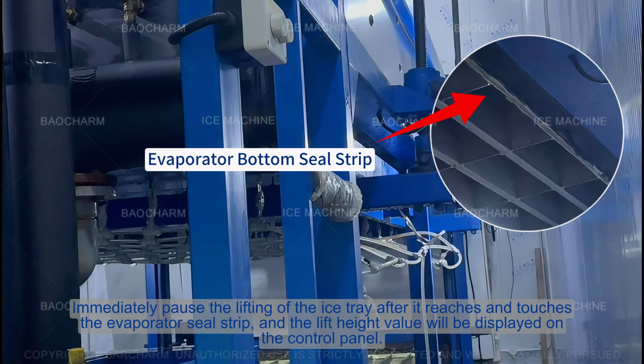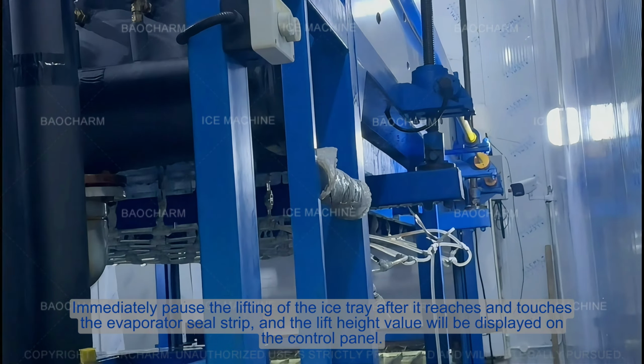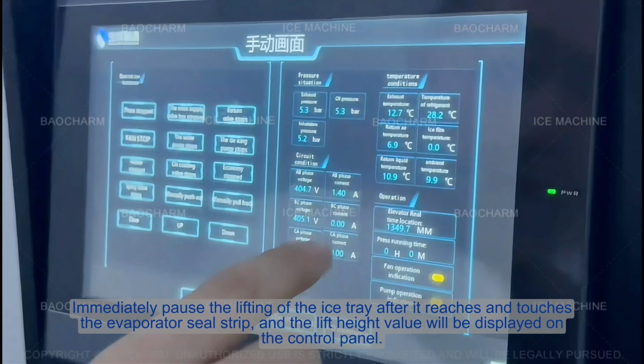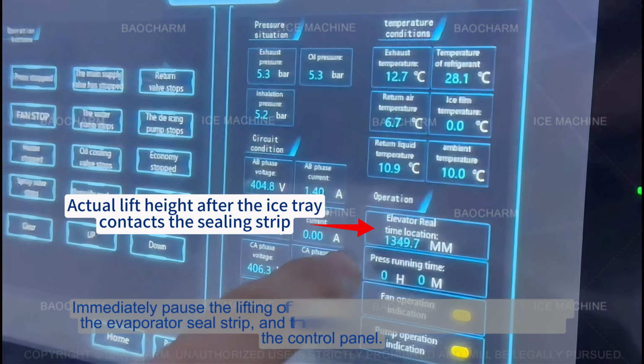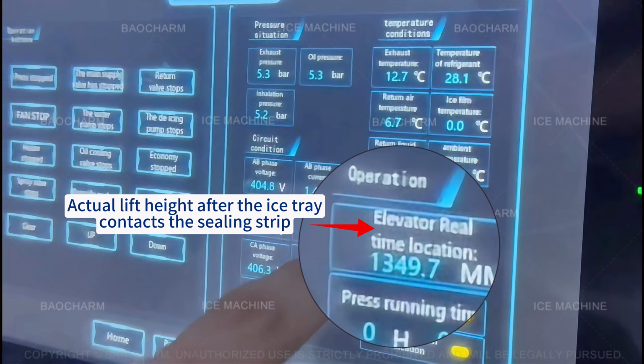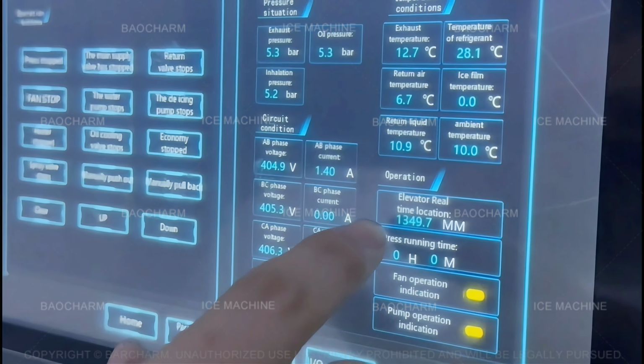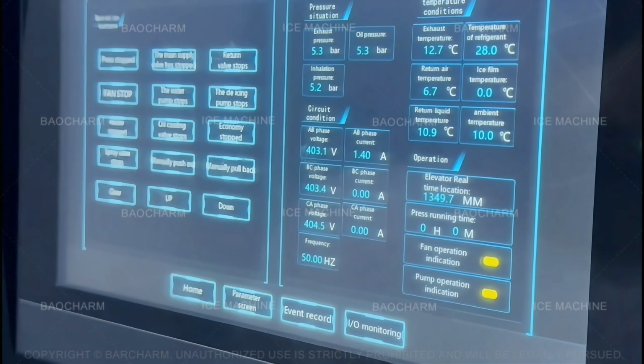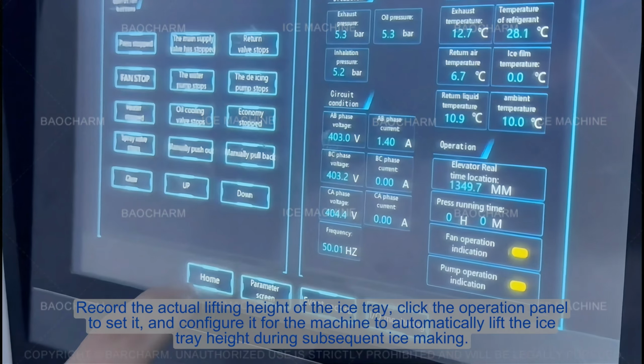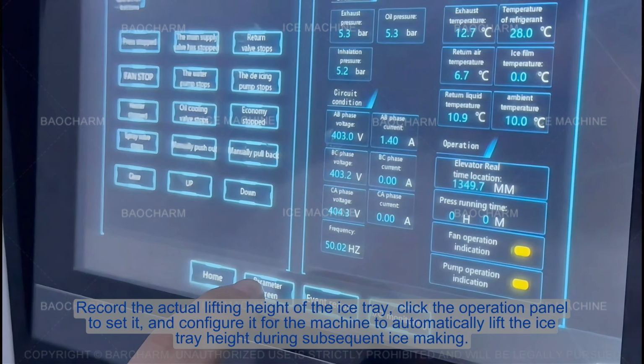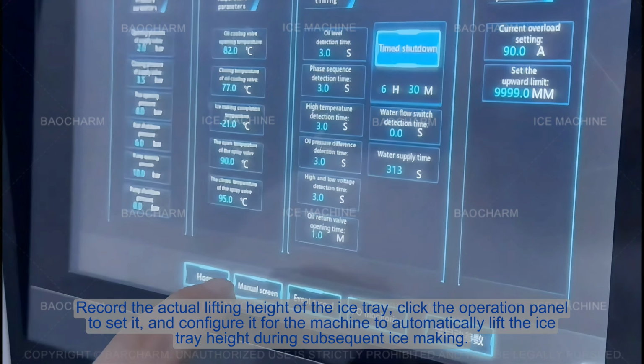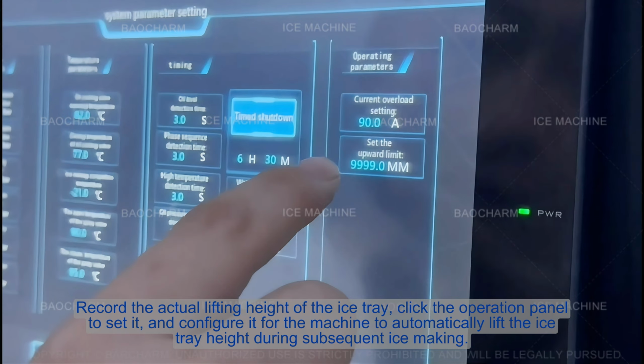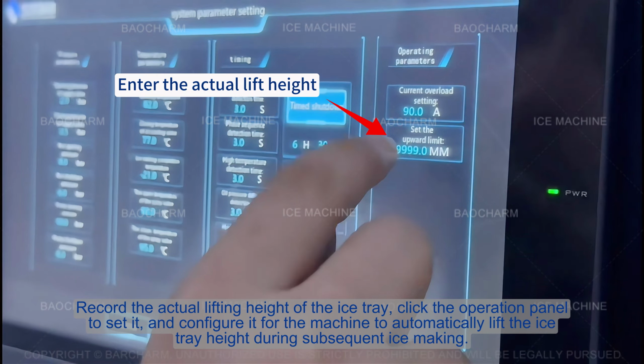Pause the lifting of the ice tray after it reaches and touches the evaporator seal strip, and the lift height value will be displayed on the control panel. Record the actual lifting height of the ice tray, click the operation panel to set it, and configure it for the machine to automatically lift the ice tray height during subsequent ice making.